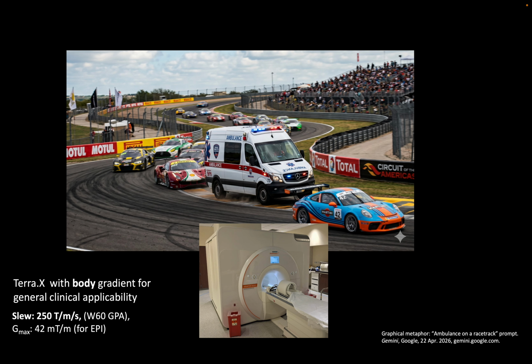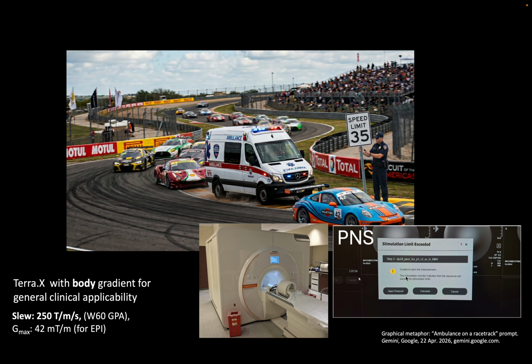The specific challenge being that these are really powerful machines. We have amazing gradient amplifier power. However, as soon as you take an ambulance to a racetrack, it kind of gets unsafe, right? You're exceeding certain safety limits. Specifically, when you even want to use maybe 30% of this gradient performance to do layer-dependent fMRI, you are being reminded that you're too bulky. You have a body gradient, you would trigger PNS. It's not safe to really use a fraction of the power of these gradients. So all we need to do now as metrology is to basically better harmonize our sequences or the reconstruction to our given hardware safety constraints.